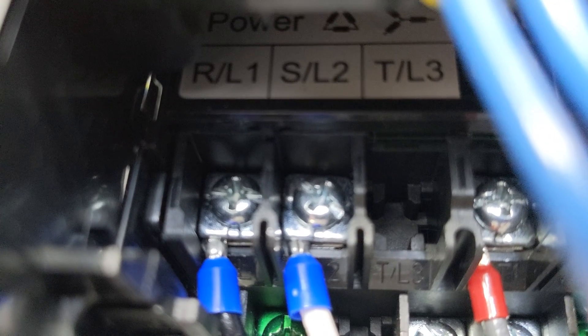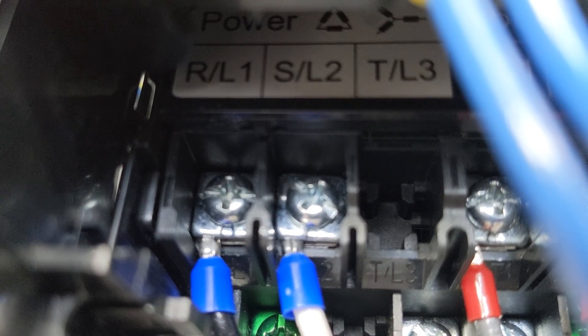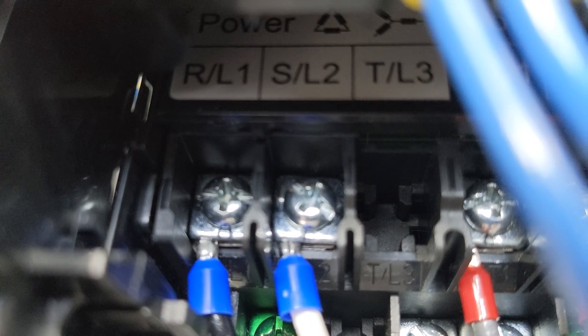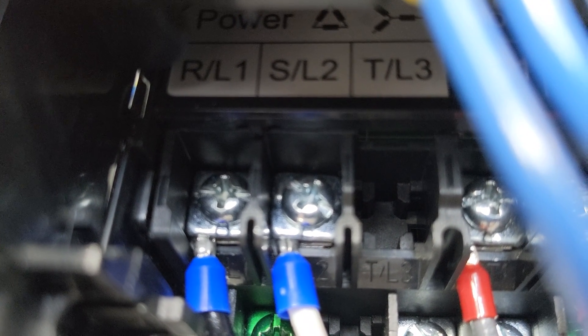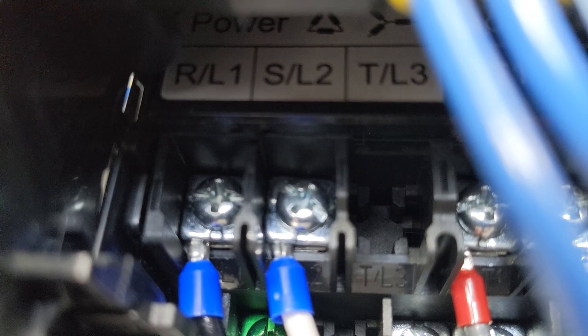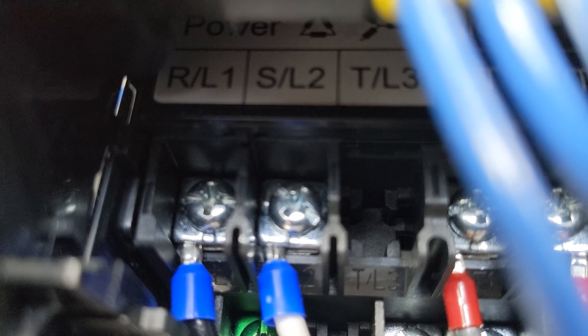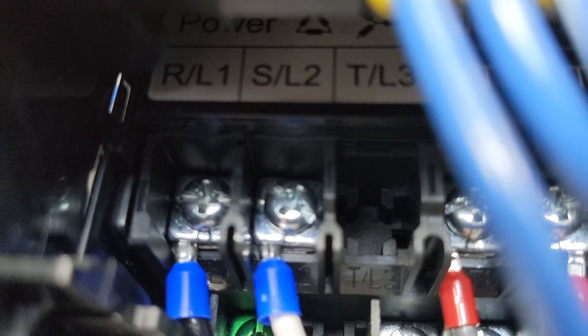On the left side of the PowerFlex, we have R/L1, S/L2, and T/L3. Now this is a single phase drive, so notice there's not even a screw on that T/L3. But here's where your incoming power comes in. And we'll measure that just as usual with our meter in AC voltage.